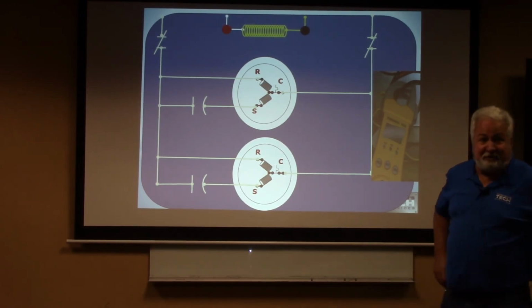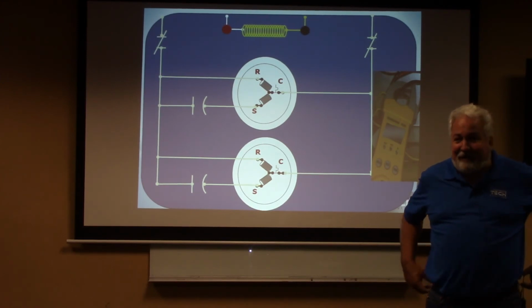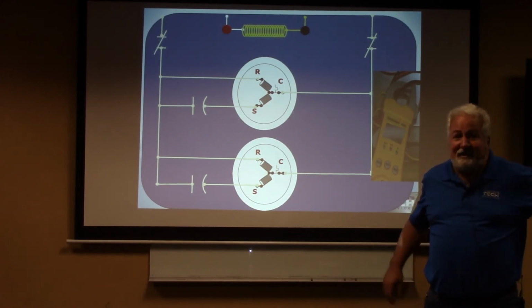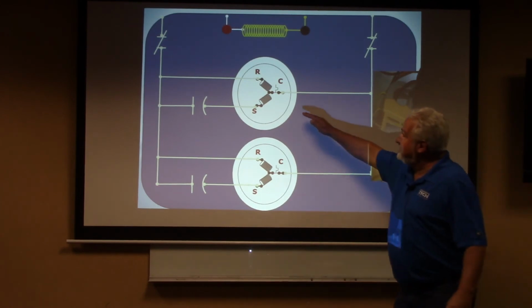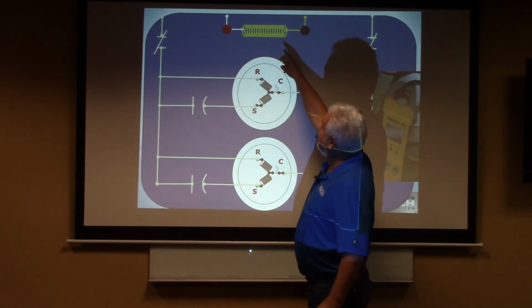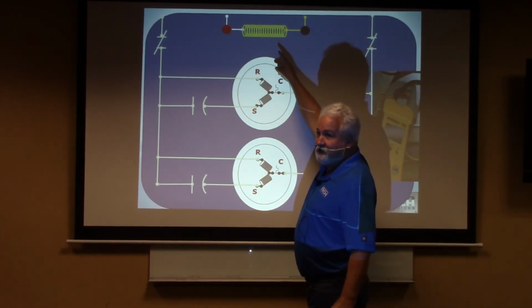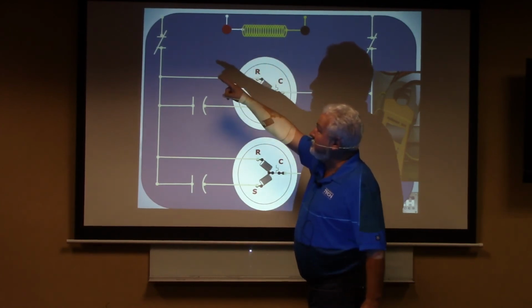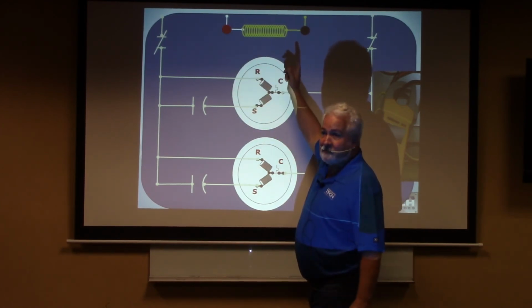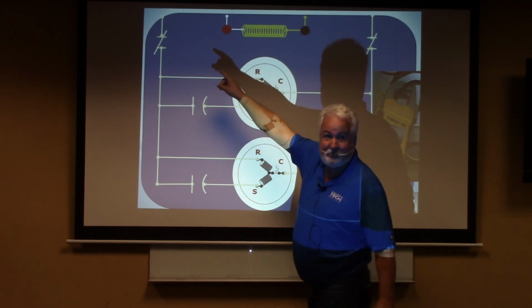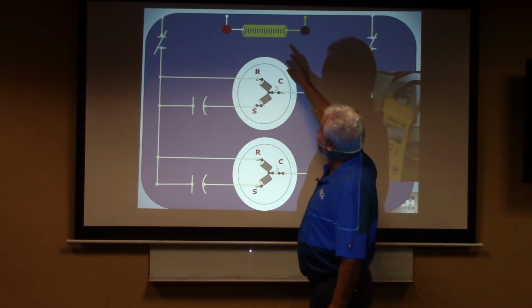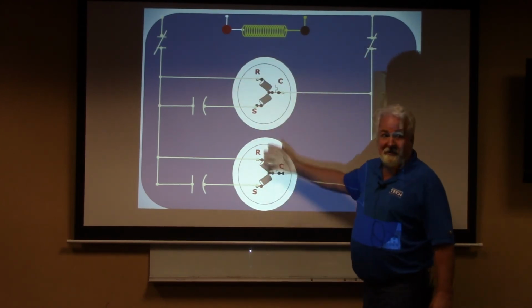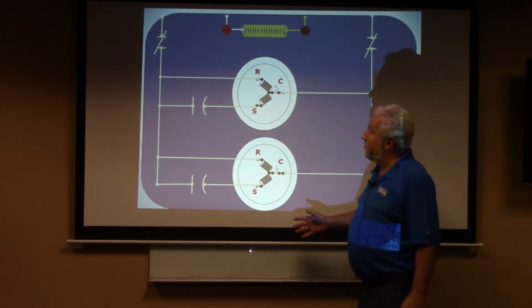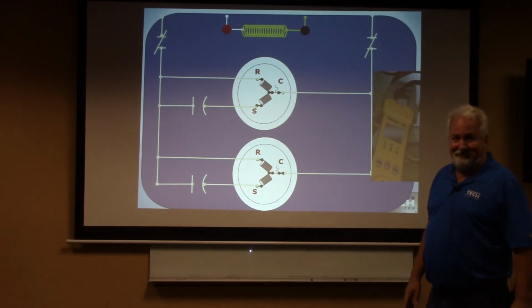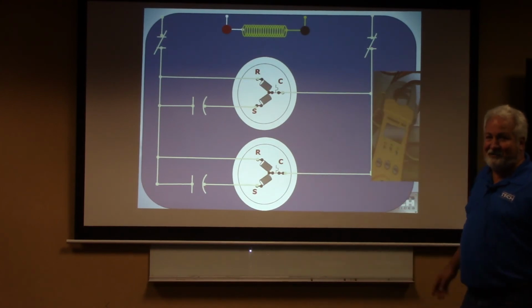Okay, there's the audience participation part of this class. Maybe I didn't get that out there. Okay, this is a condenser. Compressor, contactor coil. Is the contactor operated or not? Yes, it's operated because it's pulled in. So it's energized. What should this be doing? Running. Okay, good. So if I put my meter across the contactor coil, what should I read? 24. There we go.